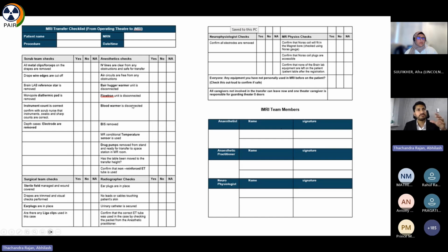Sometimes there will be infusion pumps, and these infusion pumps are not conditional for the MRI, so we have a space station where the infusion pumps should go to, and they have specific locations in the fringe field. So we have marked the lines inside the MRI examination room where these particular equipments will stay. And also the anesthetist should make sure that they are using the normal endotracheal tube, not the reinforced tube.